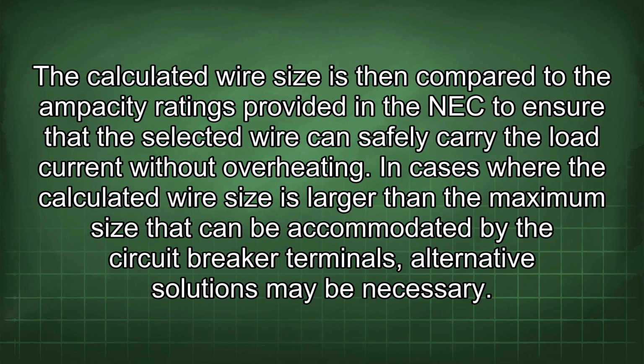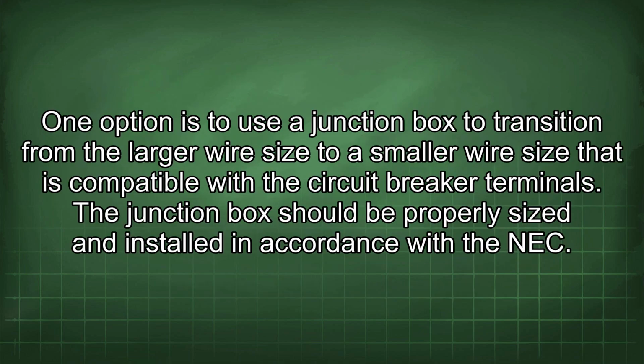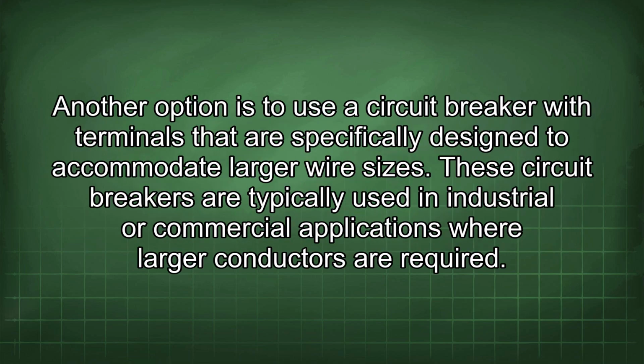In cases where the calculated wire size is larger than the maximum size that can be accommodated by the circuit breaker terminals, alternative solutions may be necessary. One option is to use a junction box to transition from the larger wire size to a smaller wire size that is compatible with the circuit breaker terminals. The junction box should be properly sized and installed in accordance with the NEC. Another option is to use a circuit breaker with terminals that are specifically designed to accommodate larger wire sizes. These circuit breakers are typically used in industrial or commercial applications where larger conductors are required.